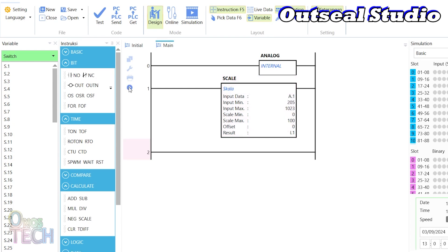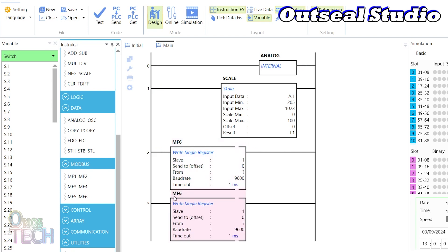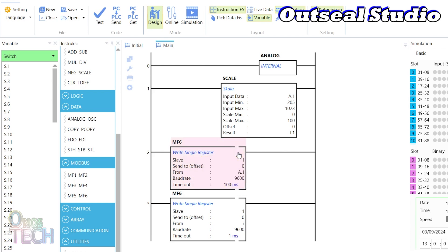Add two MF6 Modbus instructions on separate rungs. For the first, maintain slave ID 1, baud rate 9600, set the 'from' parameter to A.1, and timeout to 100 milliseconds. For the second MF6, set the slave ID to 2, the 'from' to I.1, and the timeout to 100 milliseconds.